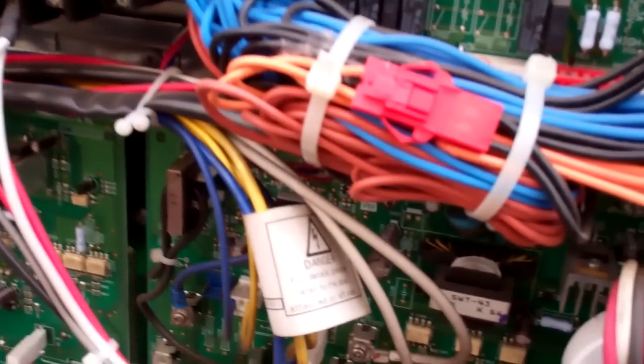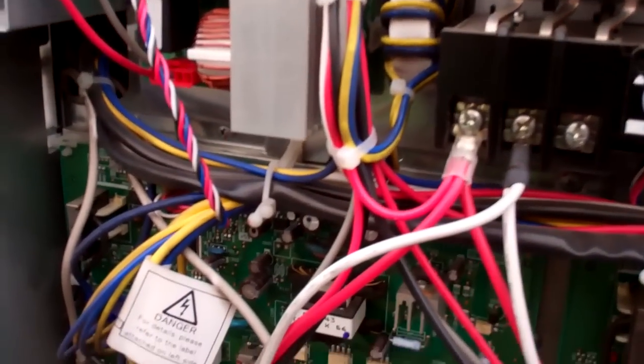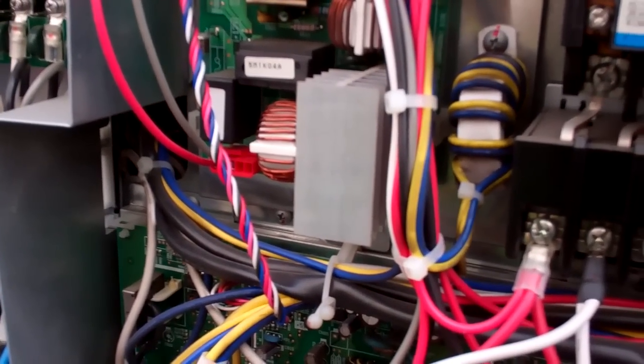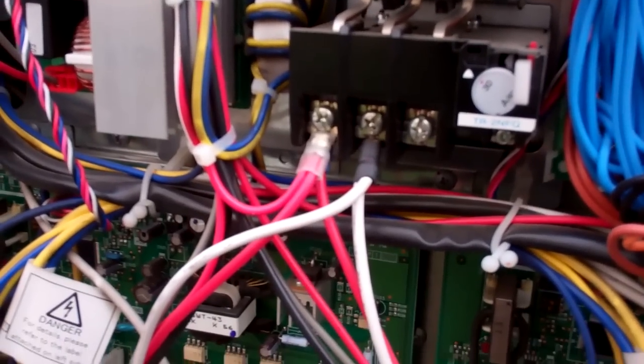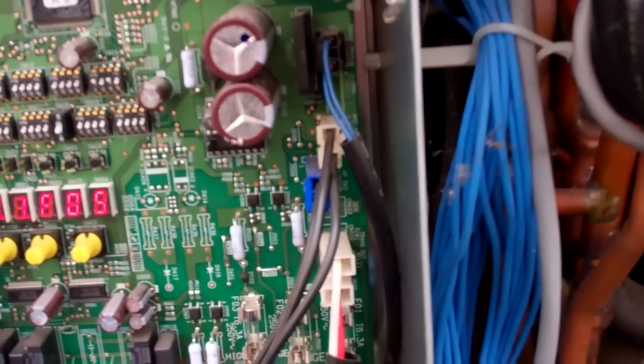So we want to turn the power off. Probably leave it for a bit if it's an inverter — you can get a nasty belt off these things until the capacitors are discharged. And then we'll unplug that sensor and compare it. I expect it should be the same as TD1.